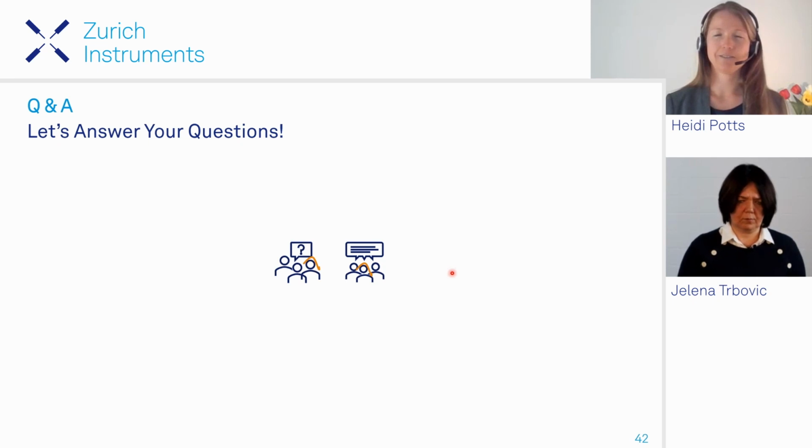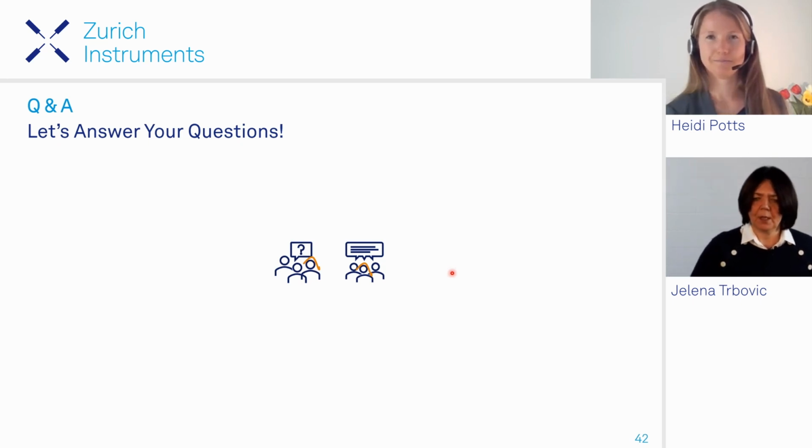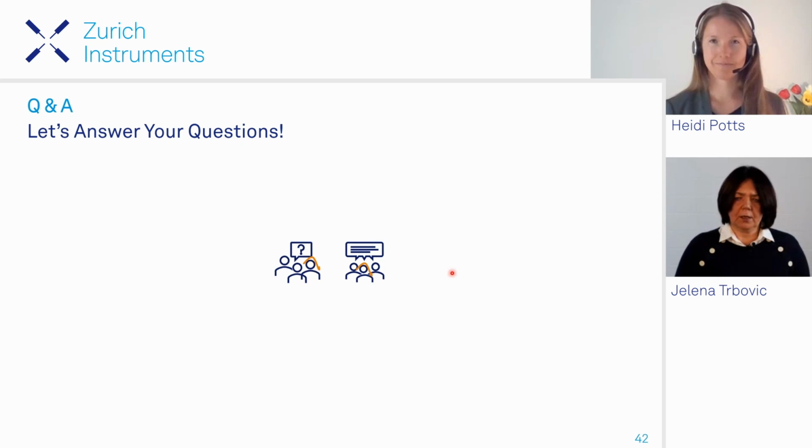And you asked about the limitation. There's actually no limitation in terms of frequency, so you can run these 8 signals at the full frequency up to 600 megahertz. Okay. Thanks a lot, Heidi.